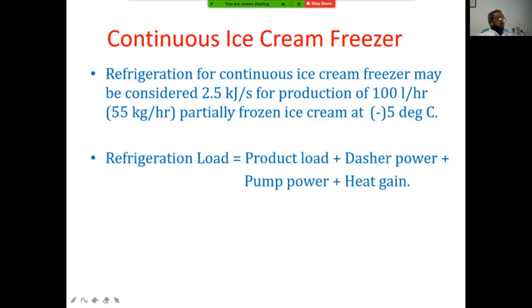To calculate the refrigerant load for the continuous ice cream freezer is somewhat complicated. How? First, we have seen the batch weight. Here the heat gain by the cylinder is required to be calculated. Again, the sensible load before freezing, the latent heat load of freezing, and the sensible cooling load after freezing are required to be calculated. Plus the power required for scraping of the ice cream is also required. And the mix is transferred from the pump to the freezing cylinder. There is a pipeline, everything. The heat gained by the pipeline, the heat added by the pump, air, everything is required to be calculated. So it's a very complicated process.